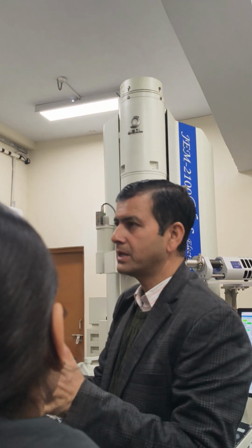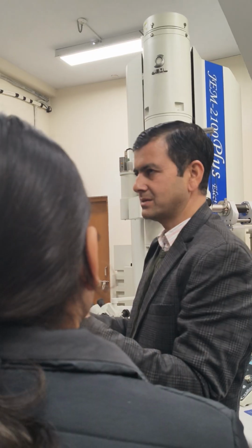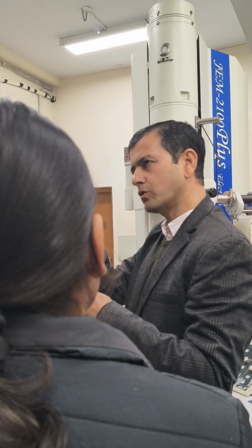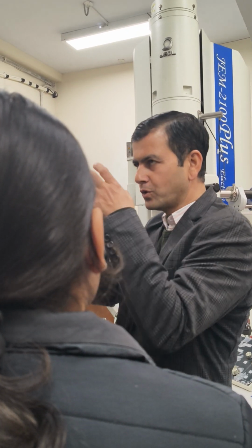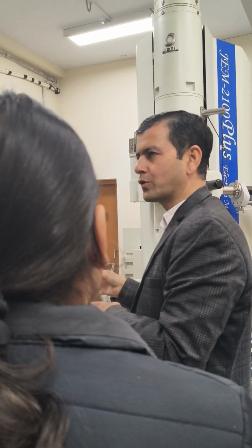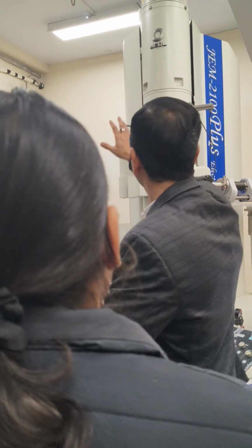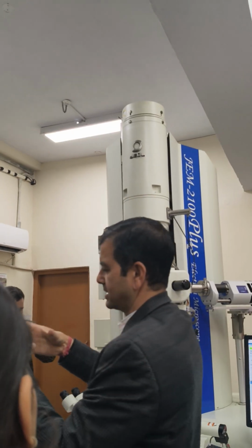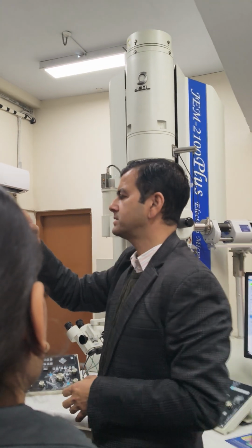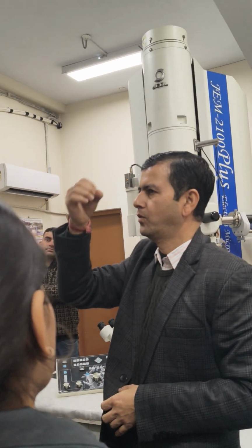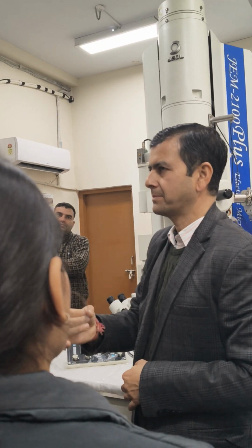As we are dealing with electrons, we need a condenser lens. A light microscope also has a condenser lens, but that is just to control the light. Here we need to control the electron beam, so we need an electromagnetic lens. The electromagnetic lens arrangement is there, with coiling. From the inside it is not big, just a hollow column, and in that, vacuum is there.